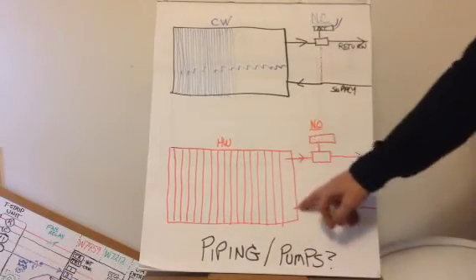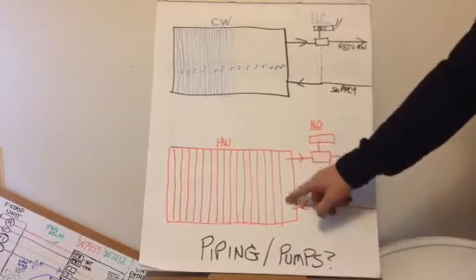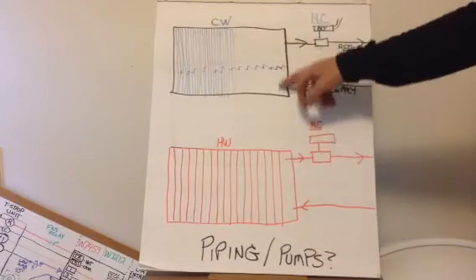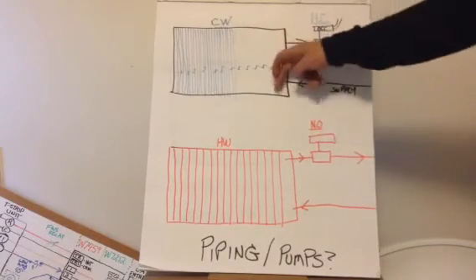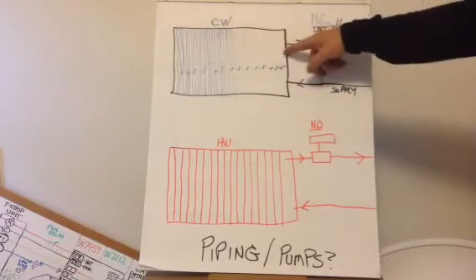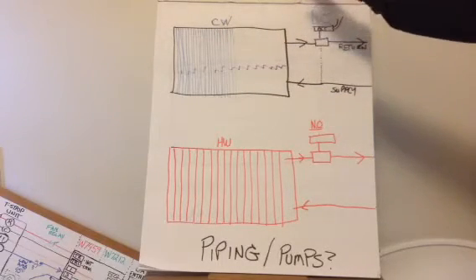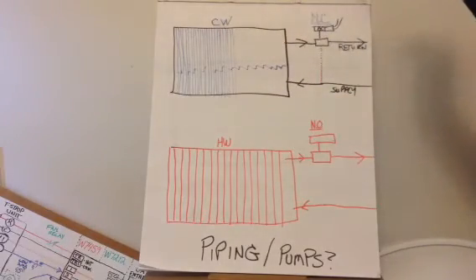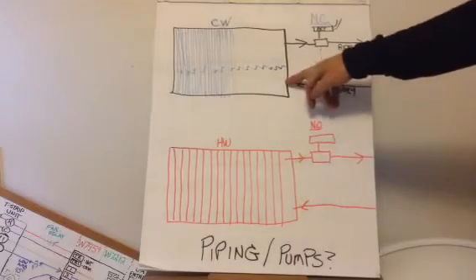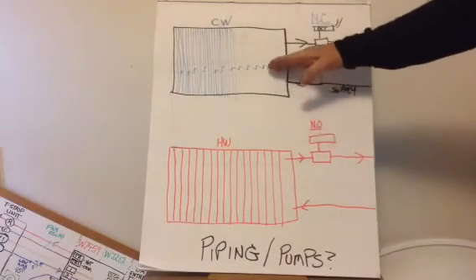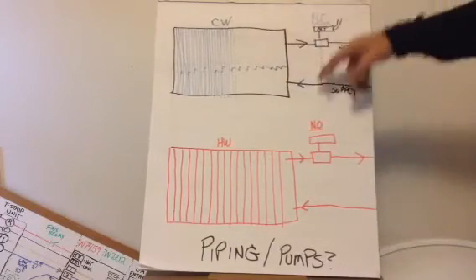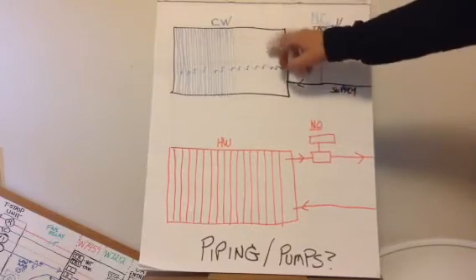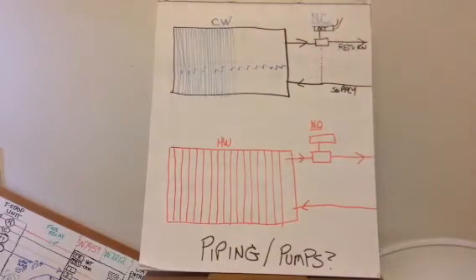but if you ran water into this coil on the top and came out the bottom, you would never fill this coil 100% with water. It would trickle down. You'd have air pockets within the tubes in there. You'd never guarantee that that coil was 100% saturated inside the tubes with liquid and not liquid mixed with air. If you run the water in the bottom, it fills the coil and pushes the air out. You will always be 100% full of water in the coil. If you're 100% full of water, you've got better heat transfer.